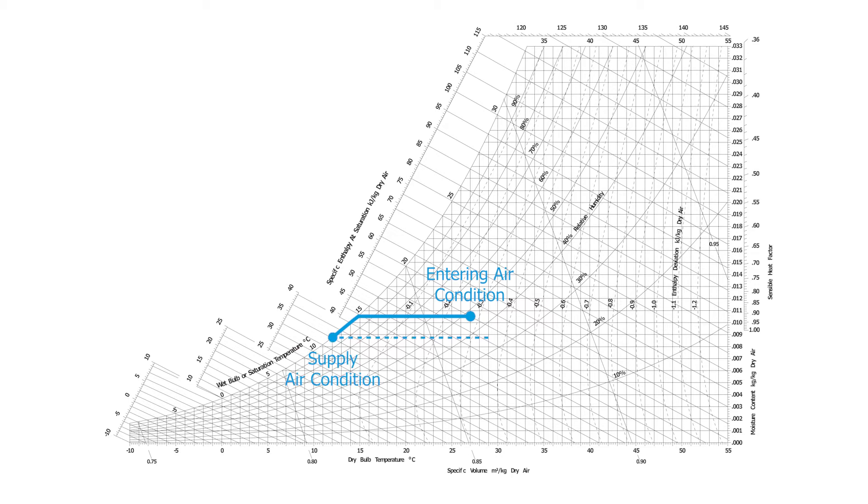As we can see from the chart, 12 degrees dew point has a moisture content of approximately 9 grams per kilogram of dry air. This supply air condition is adequate for most HVAC applications, however sometimes drier supply air is required.